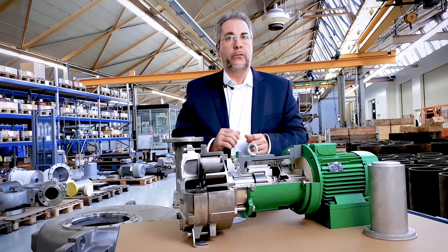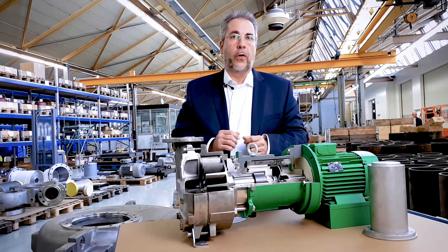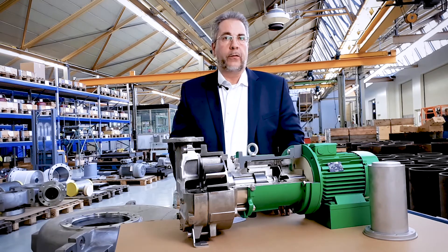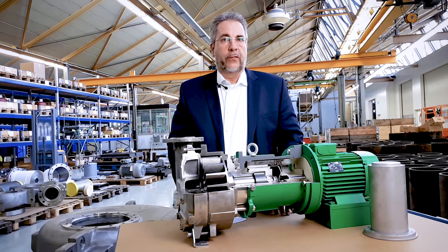This flow needs to be continuously flowing, and therefore the magnetic driven pump requires a minimum flow. This minimum flow is given in the instructions of the pump.